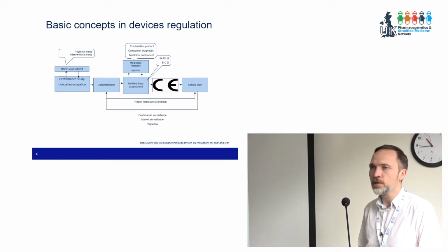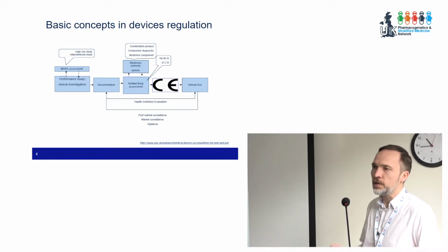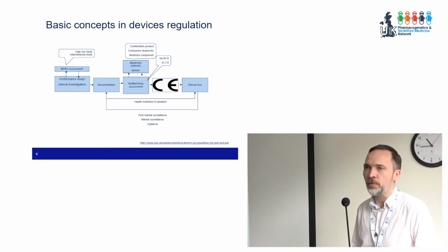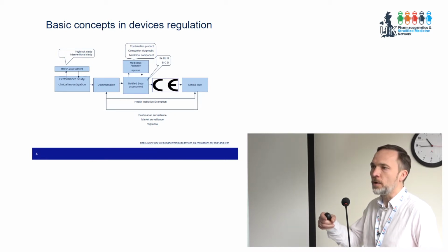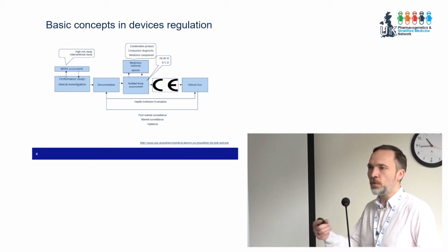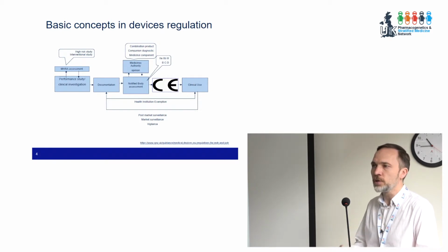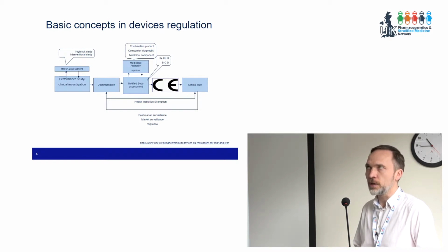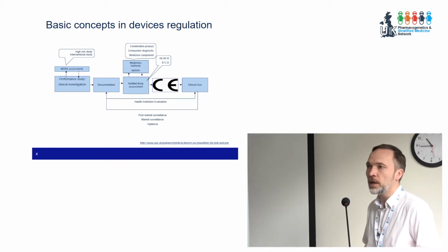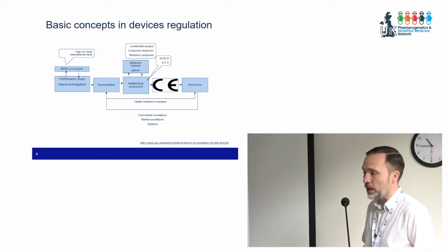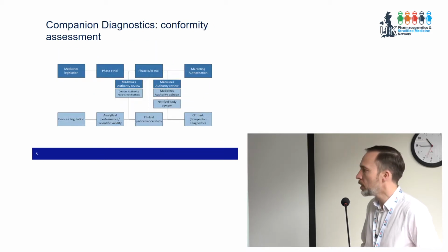It's a cyclical process. So actually, information from the device or the IVD in clinical use needs to feed back to the documentation, back to the clinical evidence. Does the device continue to perform as you intend throughout the life cycle of the device, throughout the whole lifetime of the device? And there are structures in place in the regulations which force manufacturers to do periodic summary update reports. For the high-risk devices, they will be publicly available. So in a nutshell, that's the basic concept of devices regulation.